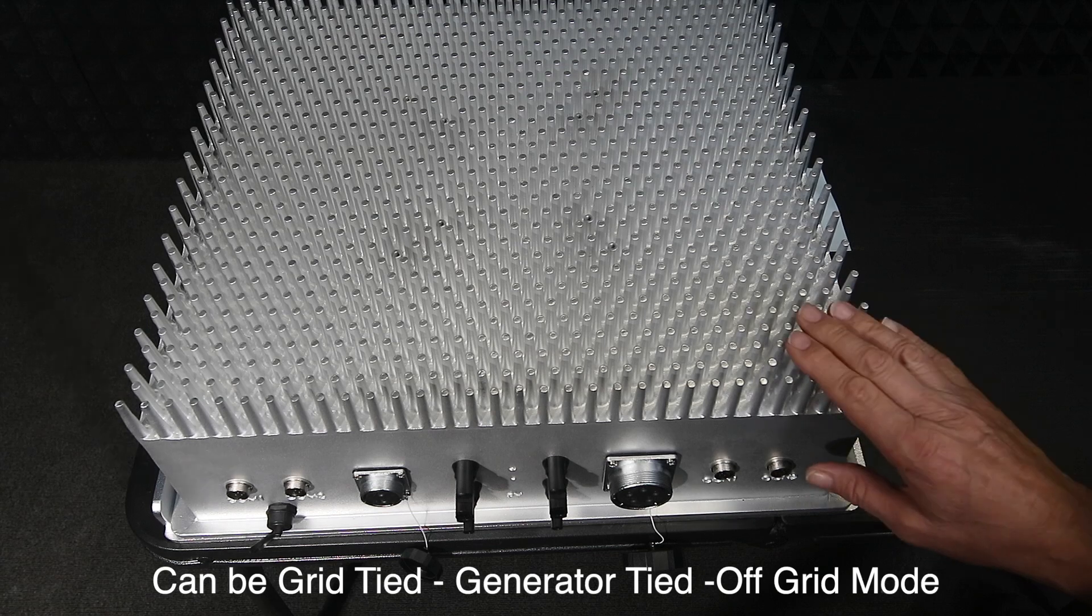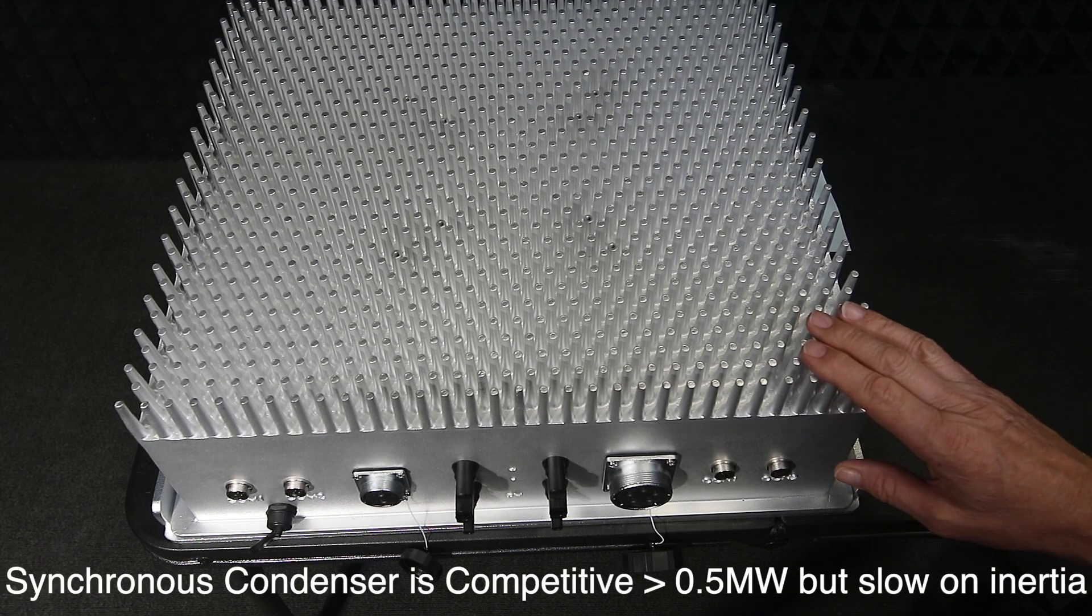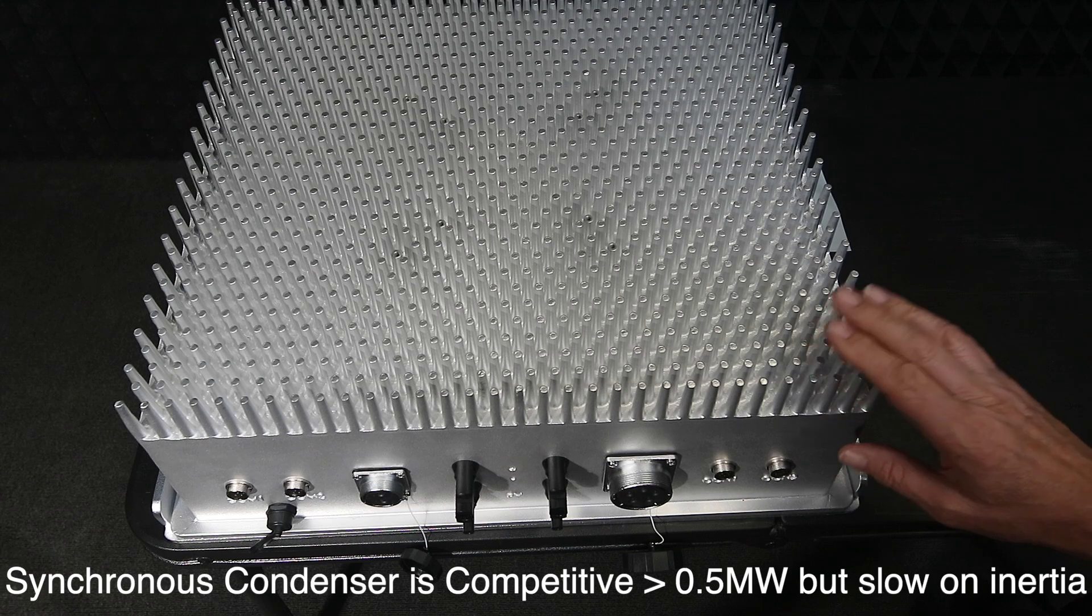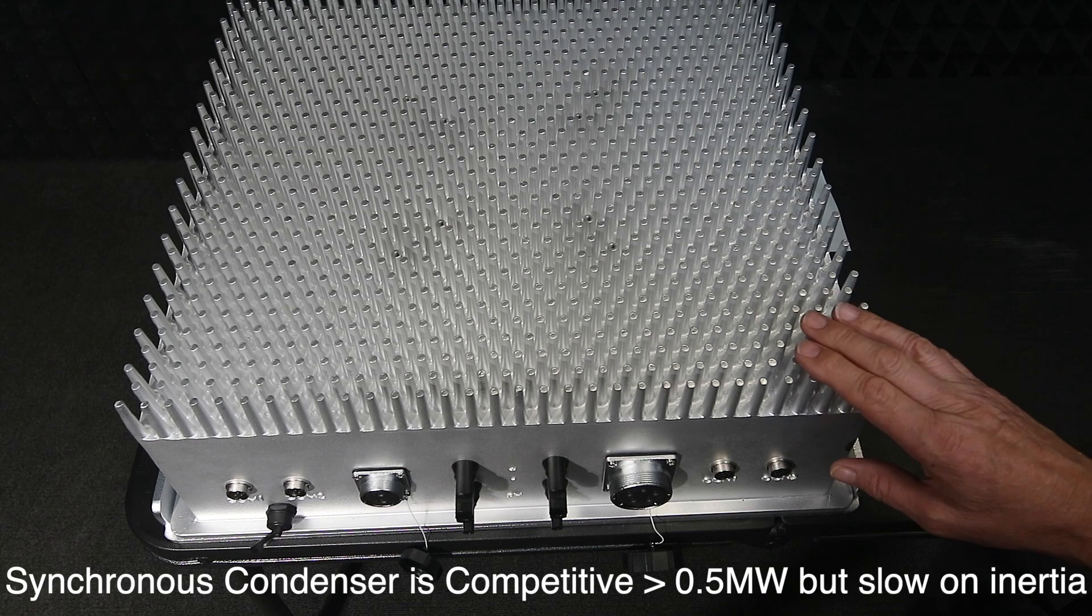The competitor to this product is a synchronous condenser. Up to about half a megawatt in capacity, this is more competitive. Above half a megawatt, as you approach one megawatt, the synchronous condenser can be more competitive.